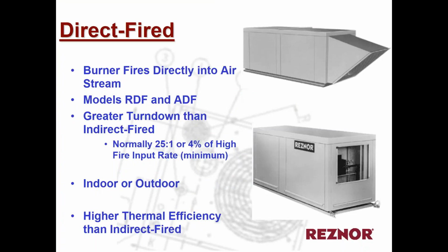So we did mention a little bit earlier direct fired. As I had stated earlier, a direct fired unit is a unit that does not have a heat exchanger in it. It's where the burner fires directly into the airstream. And why we do that is because on larger CFM jobs, particularly in process or industrial type applications, we're able to get a greater turn down. And what that is, is being able to match the gas-fired capability of the unit as the air flows through the unit to gain more efficiency through the unit. So when we're able to turn down a unit's input, we're able to garner higher thermal efficiency than an indirect fired unit. And when you get into high CFM applications, that's pretty important.